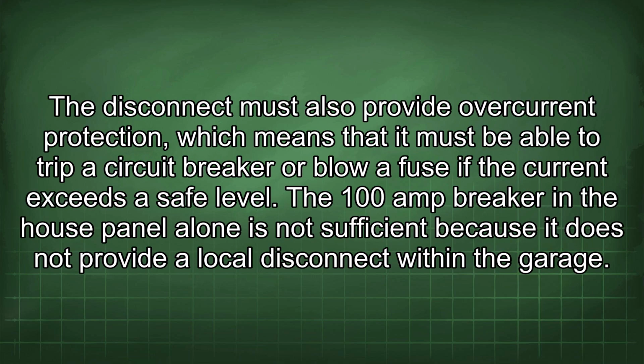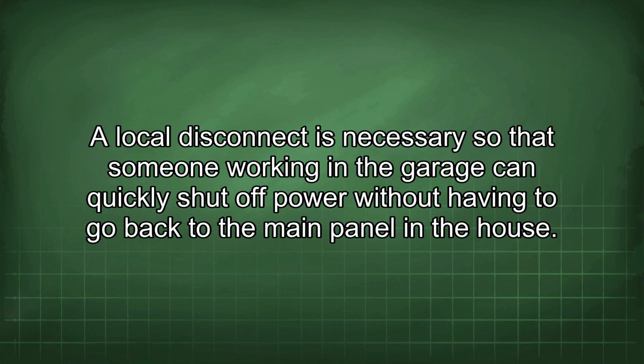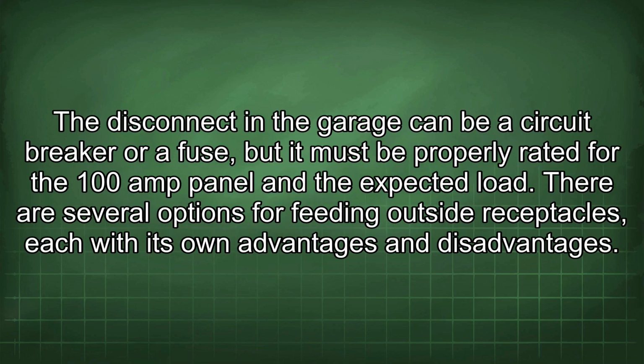The disconnect must also provide overcurrent protection, which means that it must be able to trip a circuit breaker or blow a fuse if the current exceeds a safe level. The 100-amp breaker in the house panel alone is not sufficient because it does not provide a local disconnect within the garage. A local disconnect is necessary so that someone working in the garage can quickly shut off power without having to go back to the main panel in the house. The disconnect in the garage can be a circuit breaker or a fuse, but it must be properly rated for the 100-amp panel and the expected load.